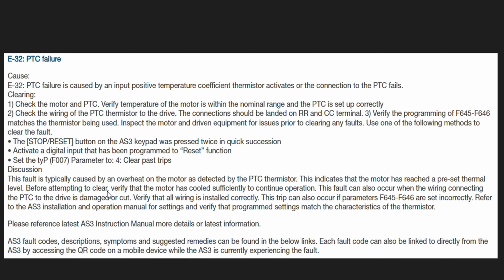Before attempting to clear, verify that the motor has cooled sufficiently to continue operation. This means when you are trying to restart your motor, your VFD again, please check that motor temperature is normal. This fault can also occur when the wiring connection from the PTC to the drive is damaged. So there will be wiring between the PTC and VFD. You need to check that also, that the wiring is proper and the PTC sensor is not damaged. So you need to cut and reinstall all the wiring.